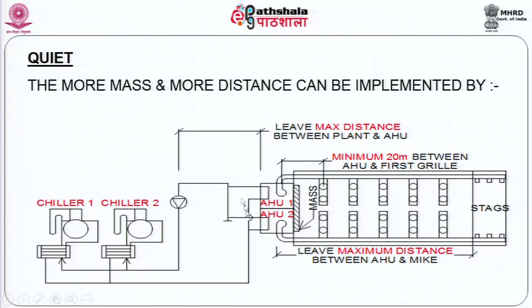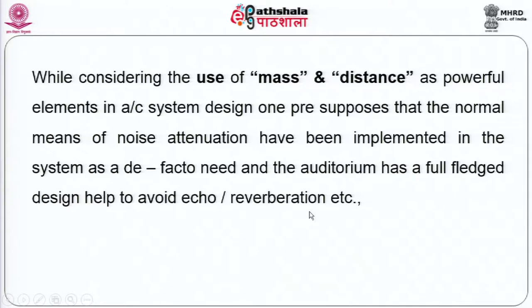The cooling equipment, the noisy equipment, the chillers and all that are kept as far away as feasible. The air handling unit cannot be kept far away. It is kept very close to the cooling area, but in between you put mass. So, here is a play of the two parameters that are required: mass to attenuate AHU noise and distance to attenuate the chiller noise. Now, this is an extremely important criterion to be kept in mind while placing equipment and designing placement of equipment for an auditorium.